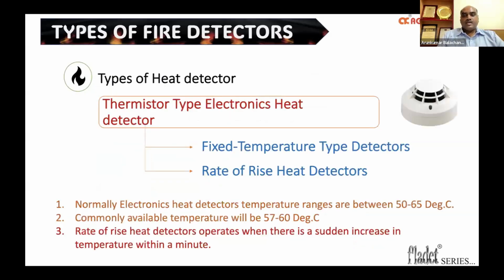The thermistor type electronic detectors use thermistors, and two classifications are there. One is a fixed temperature type, and the second is a rate of rise type. These are normal electronic heat detectors, and mainly they are in the range of 50 to 60 degrees centigrade only. The rate of rise detector will operate whenever there is a sudden increase in temperature of around 8 degrees centigrade in a single minute. Then the rate of rise detector will give an alarm. It will not wait for the set point of 60 degrees centigrade.